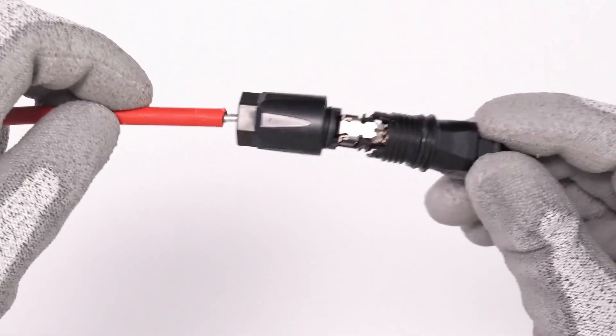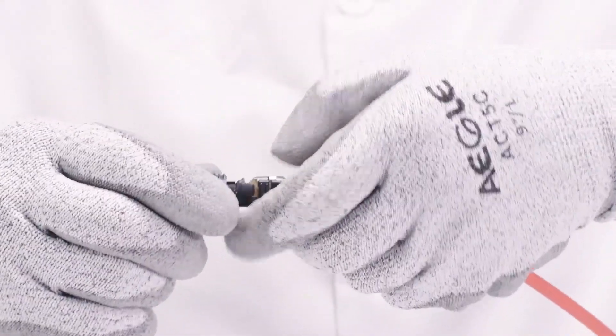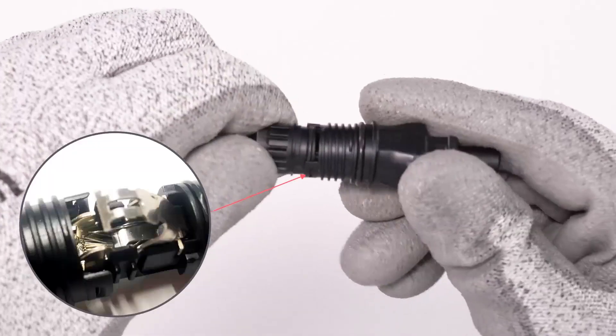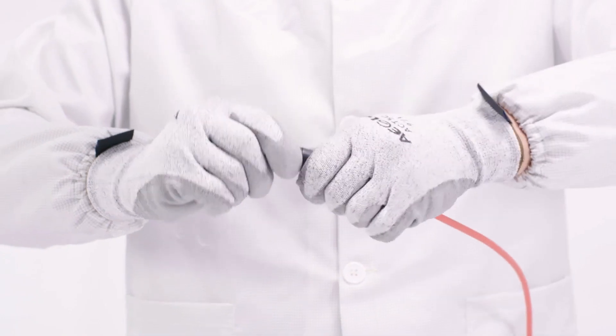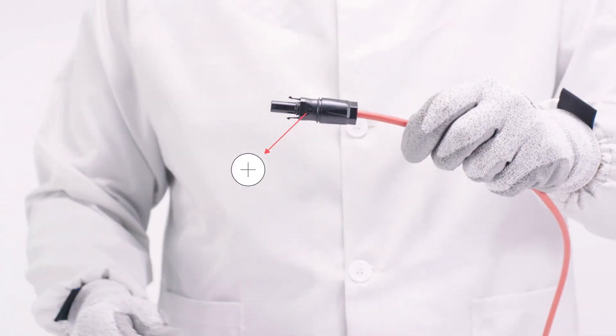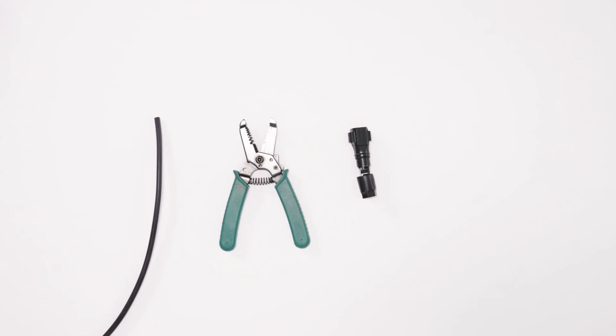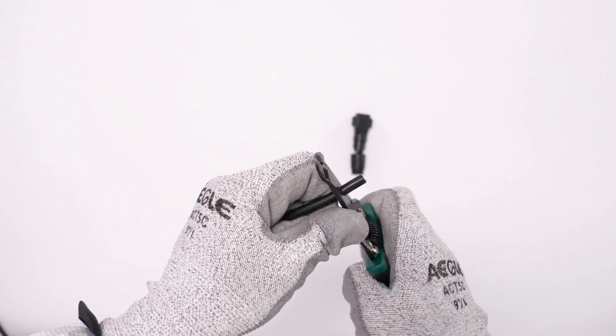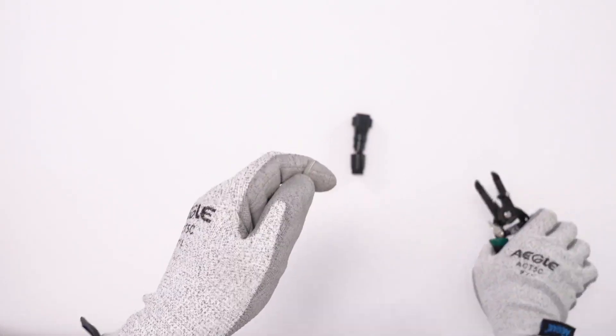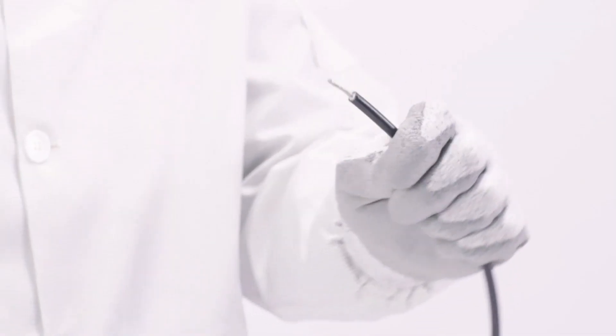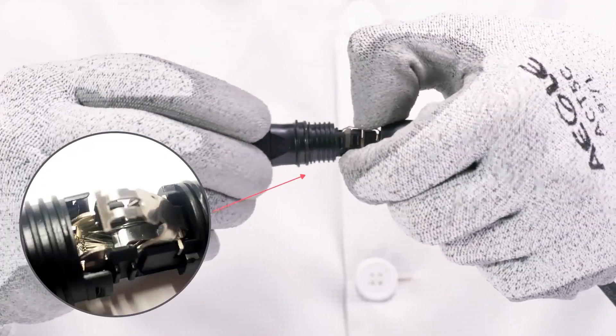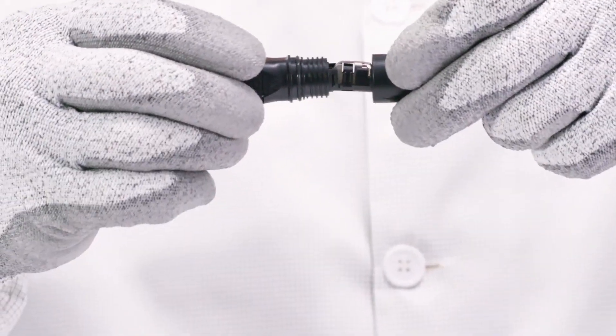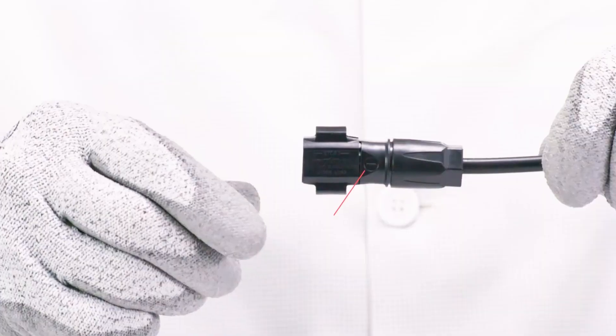Route the stripped cable all the way into the DC connector. Ensure that the stripped cable and the DC connector have the same polarity. Press the clamping bracket down until it audibly snaps into place. Ensure that the cable is correctly positioned. Push the swivel nut up to the thread and tighten.